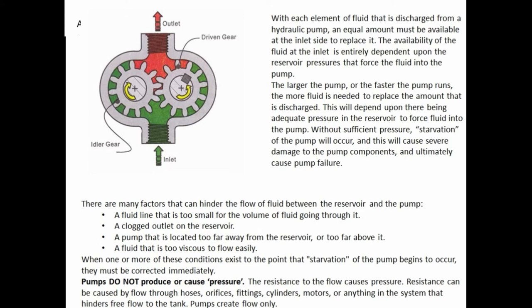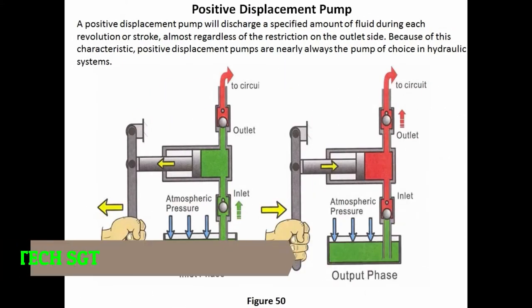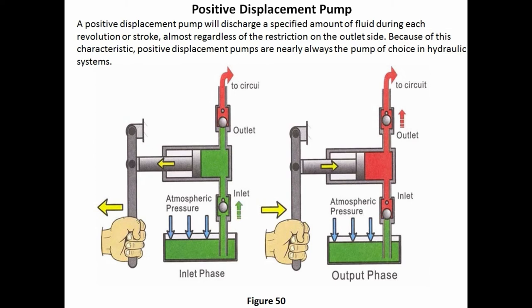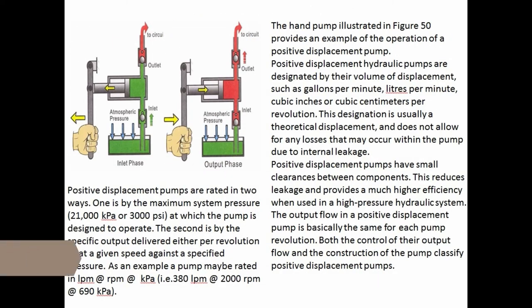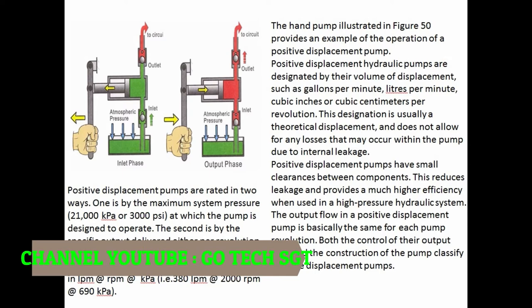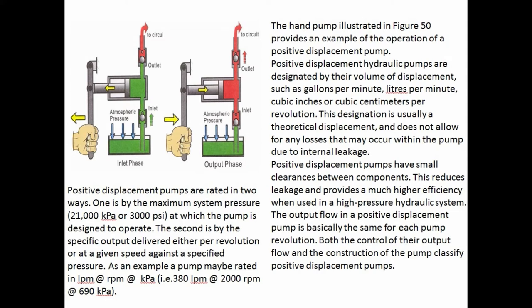A positive displacement pump will discharge a specified amount of fluid during each revolution or stroke, almost regardless of the restriction on the outlet side. Because of this characteristic, positive displacement pumps are nearly always the pump of choice in hydraulic systems. Positive displacement hydraulic pumps are designated by the volume of displacement — gallons per minute, liters per minute, cubic inches, or cubic centimeters per revolution. This designation is usually a theoretical displacement and does not allow for losses that may occur within the pump due to internal leakage.